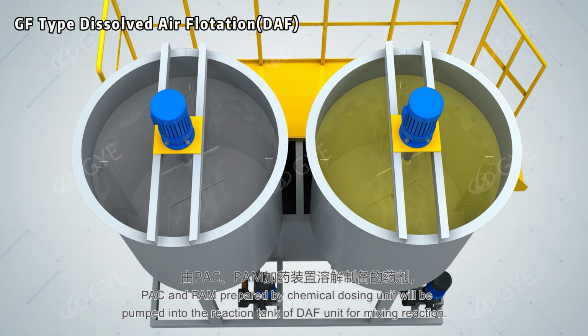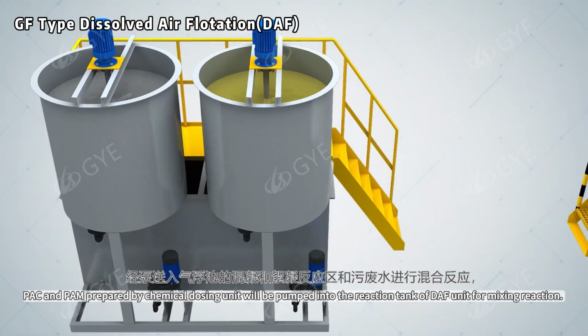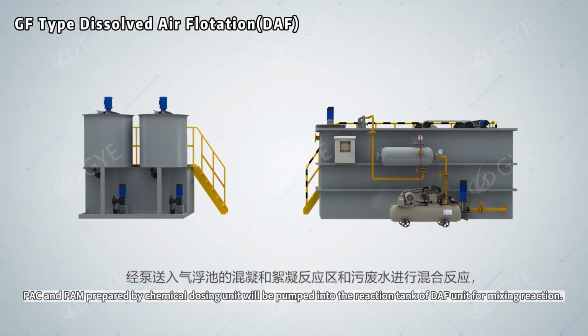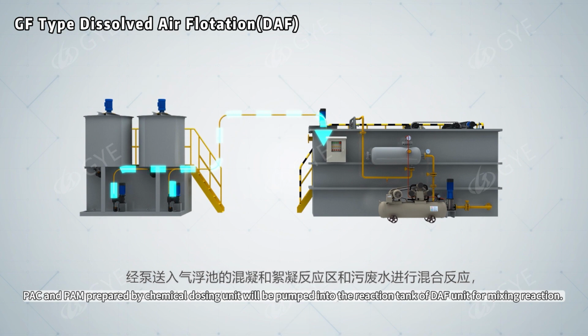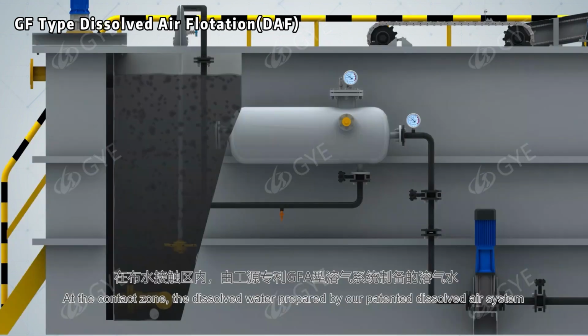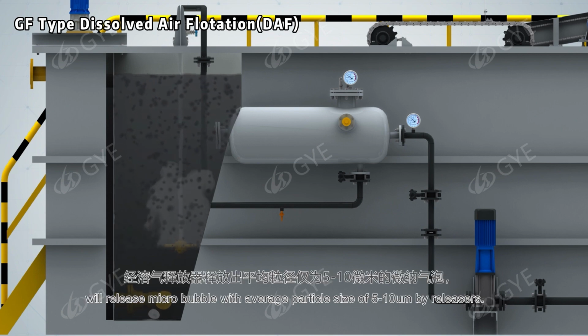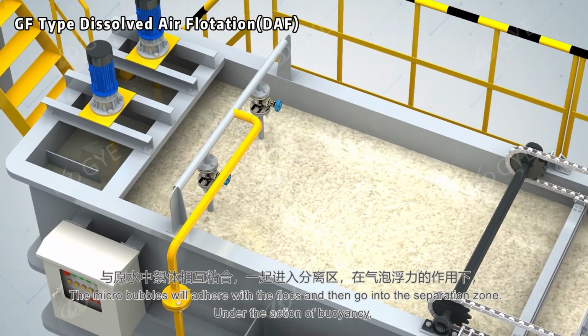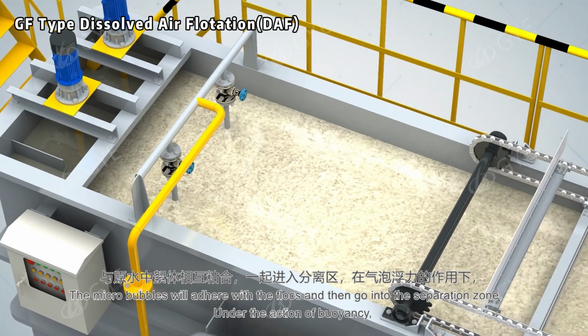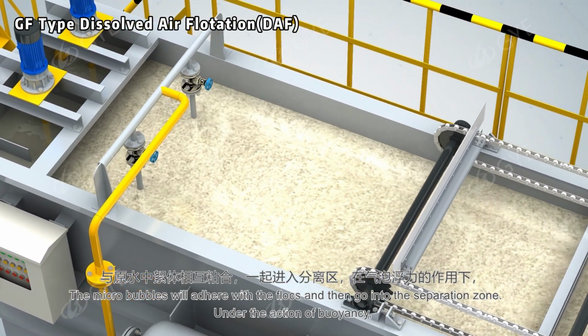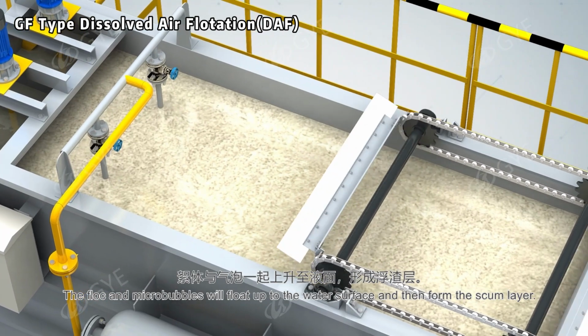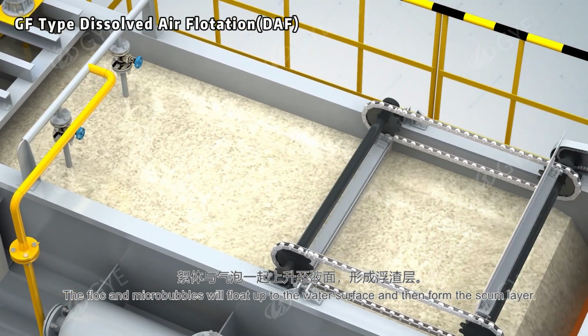PAC and PAM prepared by chemical dosing unit will be pumped into the reaction tank of DAF unit for mixing reaction. At the contact zone, the dissolved water prepared by our patented dissolved air system will release microbubbles with average particle size of 5-10 μm by releasers. The microbubbles will adhere with the floc and then go into the separation zone under the action of buoyancy. The floc and microbubbles will float up to the water surface and then form the scum layer.